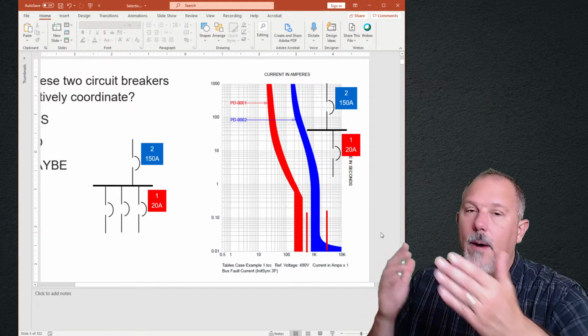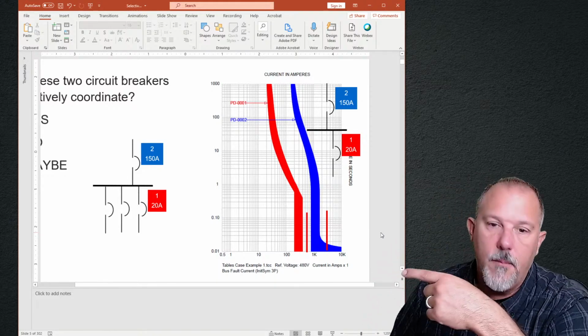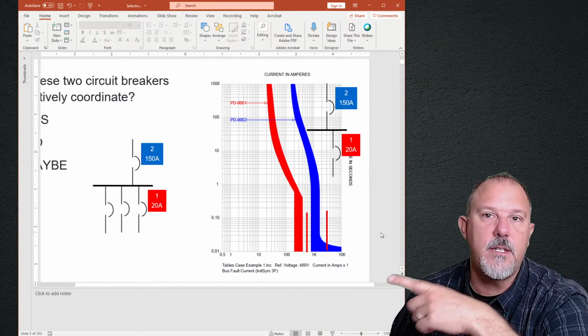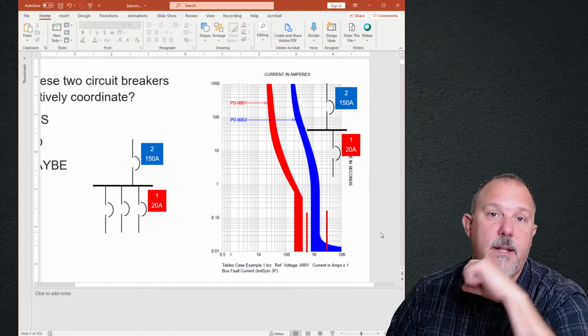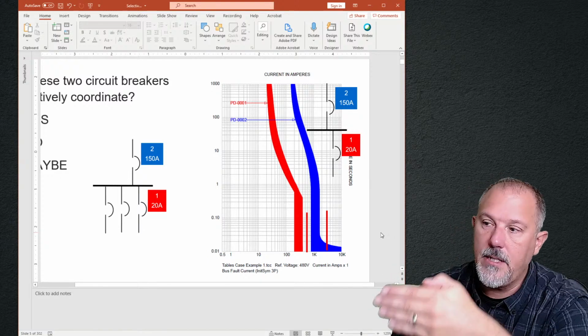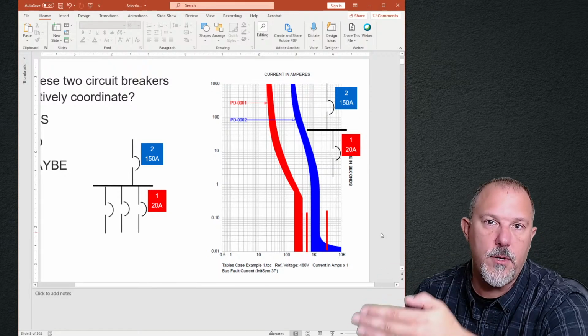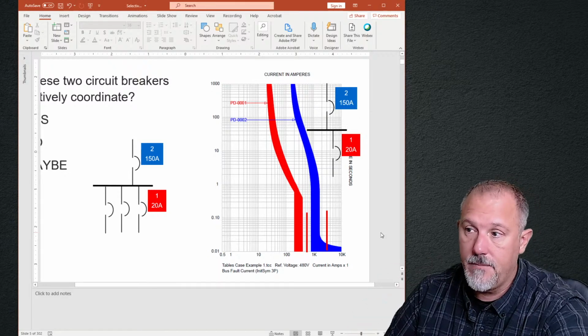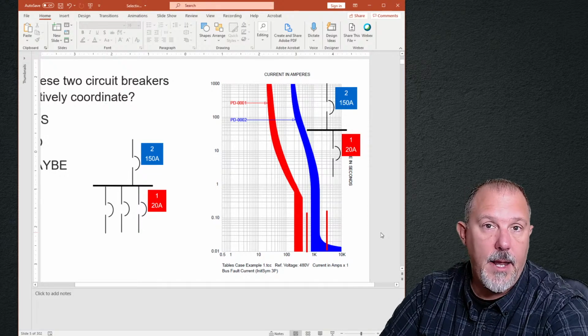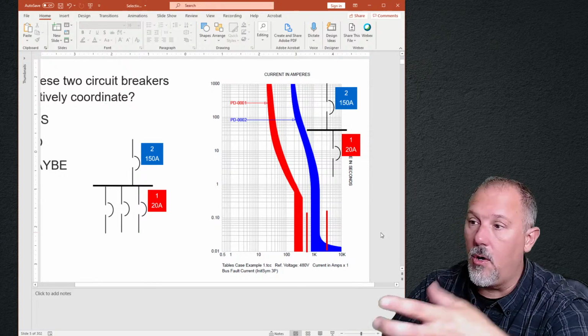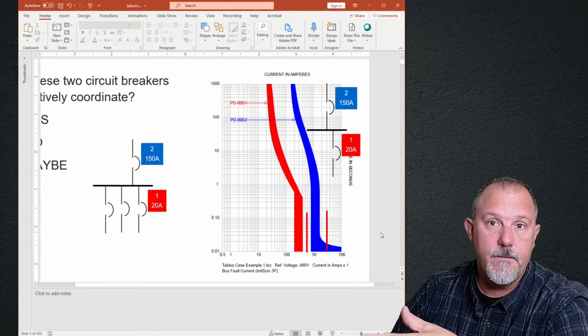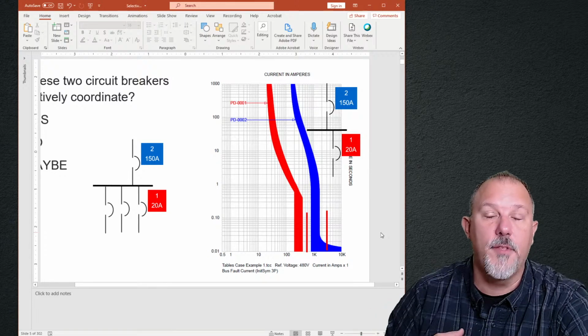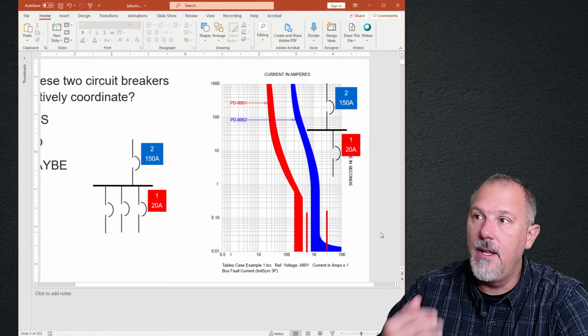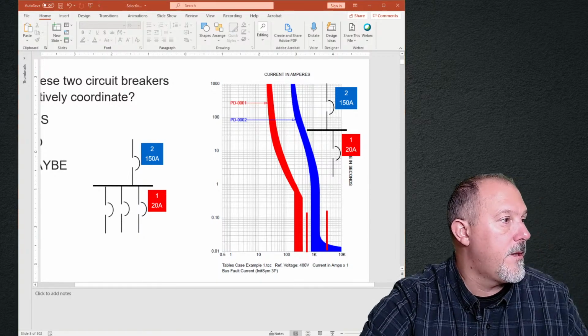0.01. So why do we use the term 0.01 seconds? 0.01 seconds is the bottom of this TCC curve. Why is it 0.01 seconds? Why does the TCC curve cut off at 0.01 seconds? SKM, EDSA, and EasyPower all default to 0.01 seconds. I could plot it lower than 0.01 seconds if I wanted to. In fact, the TCC curve.